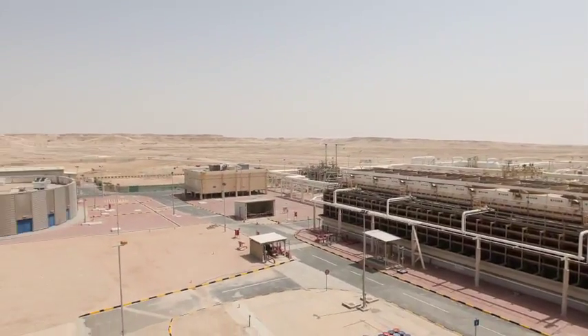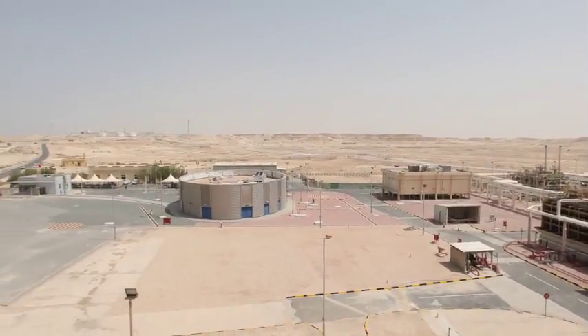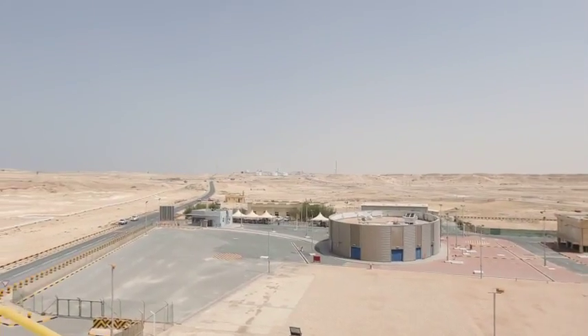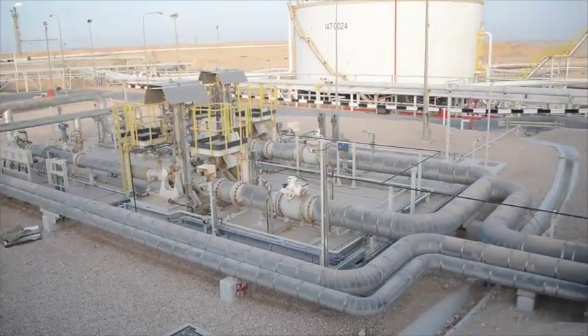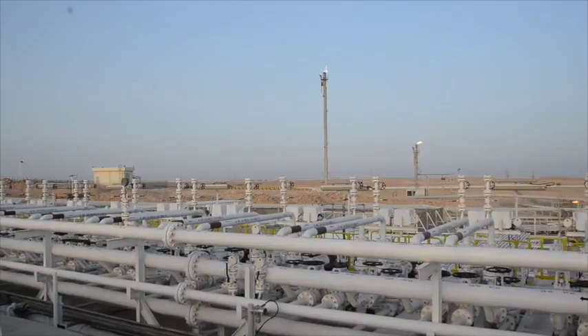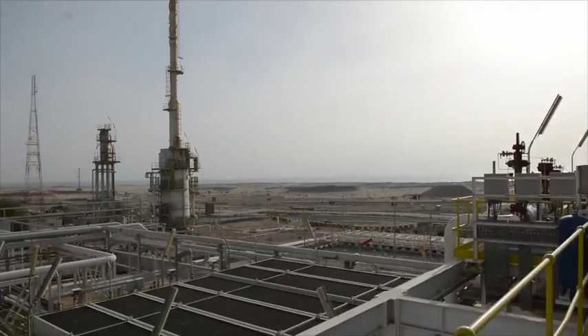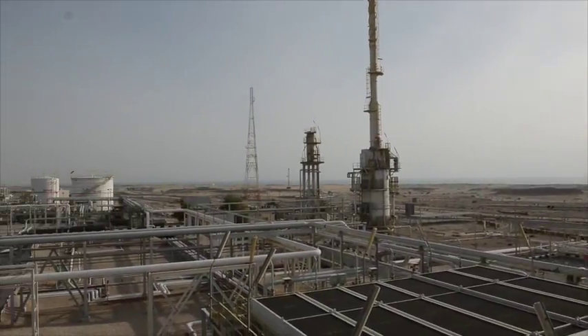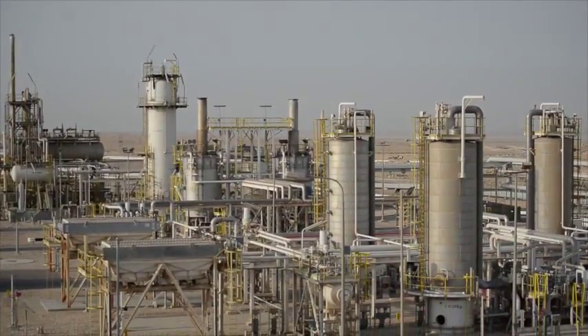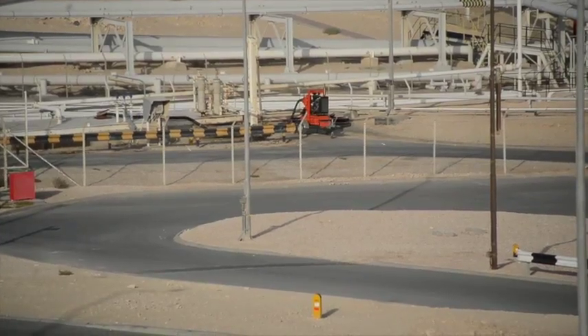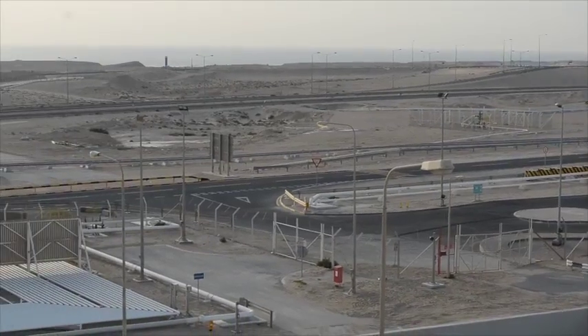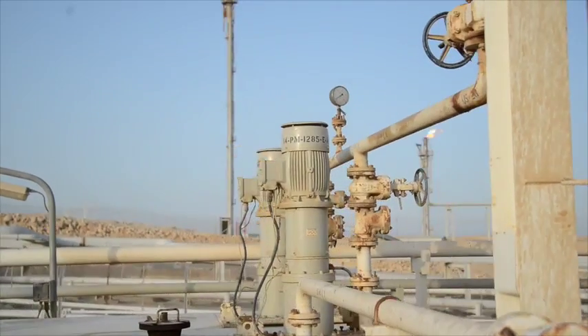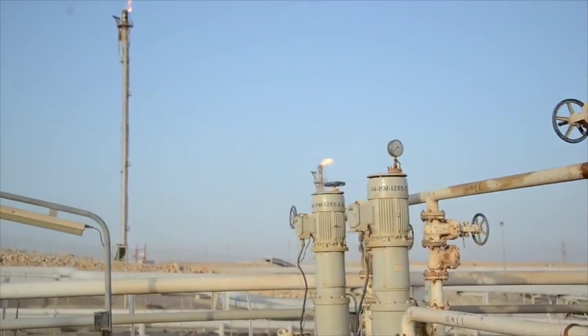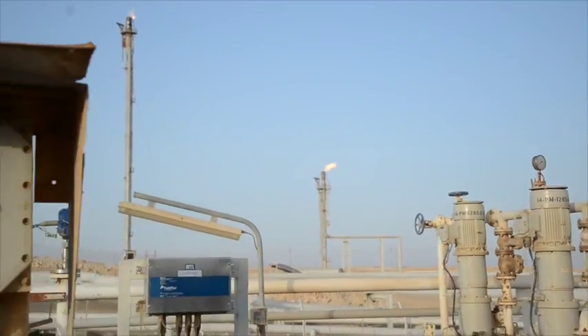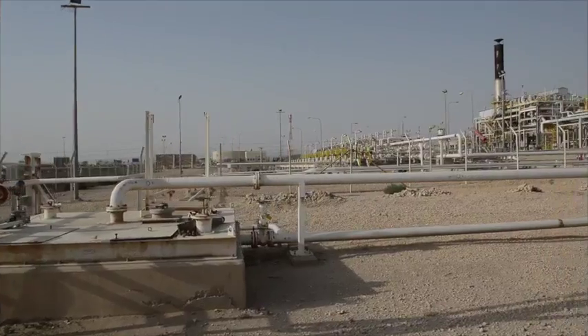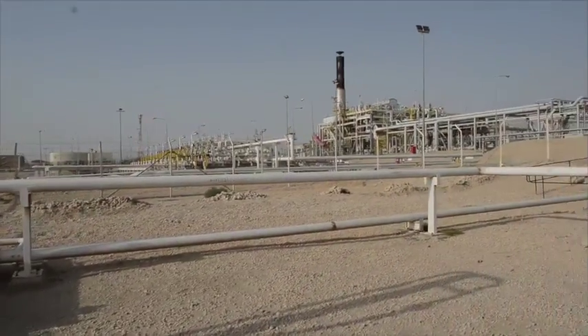The Fahahil main drains system consists of a main 4-inch header which services the drains from the separation systems, degassing systems, heat exchangers and manifolds. The system has three sections to drain hydrocarbons, hot oil and glycol respectively. The drain header is routed to one of the two drain sumps. The east sump is equipped with two drain pumps which recycle the contents of the sump to the desalting tanks, while the west sump unloads its contents directly to a road tanker via a single pump.